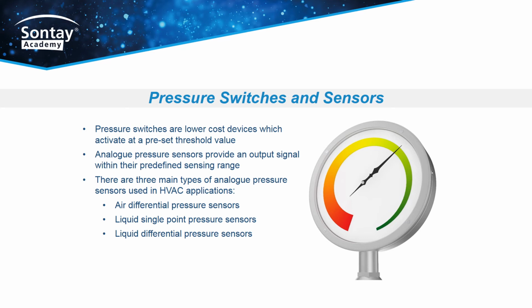However, it is worth mentioning pressure switches as there are a particularly high number of these low-cost devices used to monitor flow status and filter dirty indication throughout HVAC applications. Like their switched counterparts, pressure sensors have either a diaphragm or piezo-resistive element, which reacts to pressure being exerted upon it. We see the three main variants of pressure sensor used for HVAC applications.